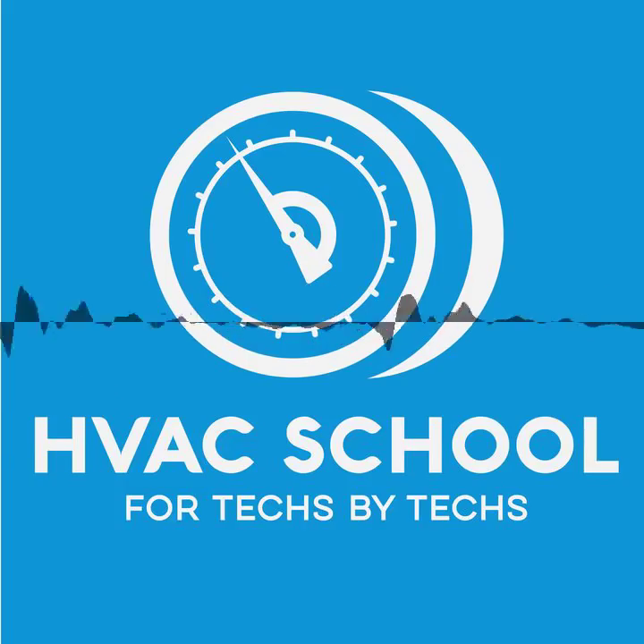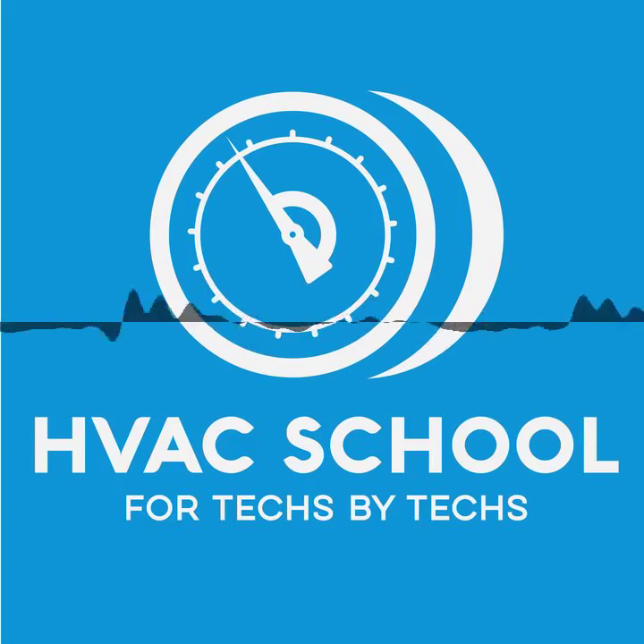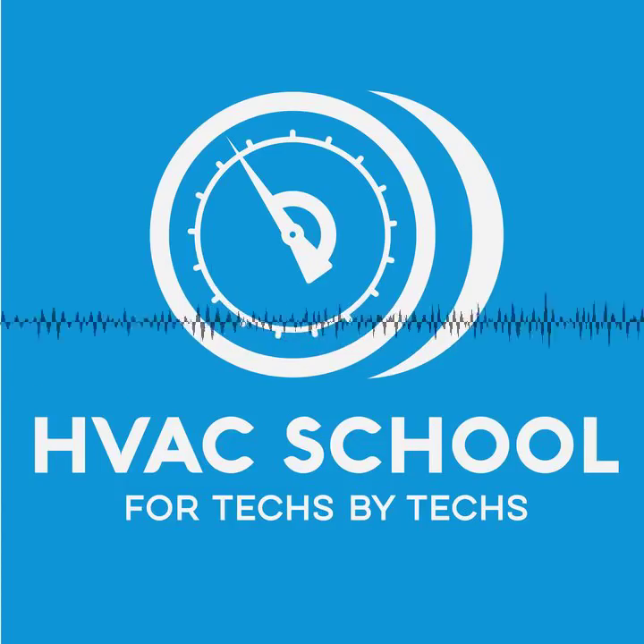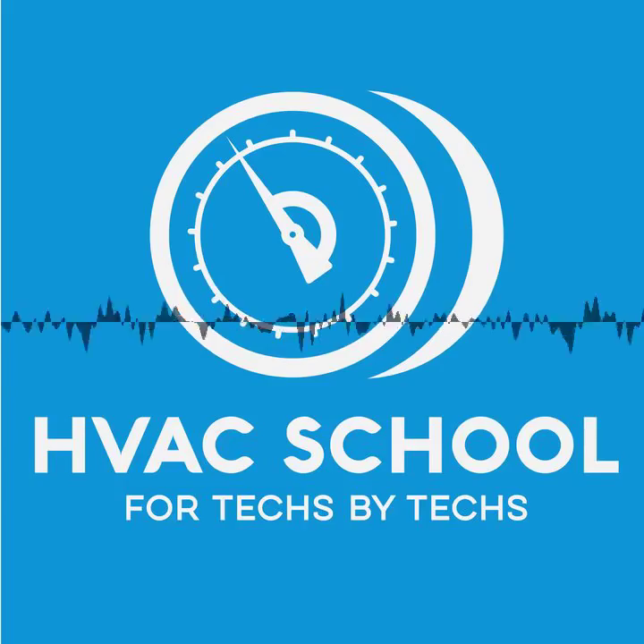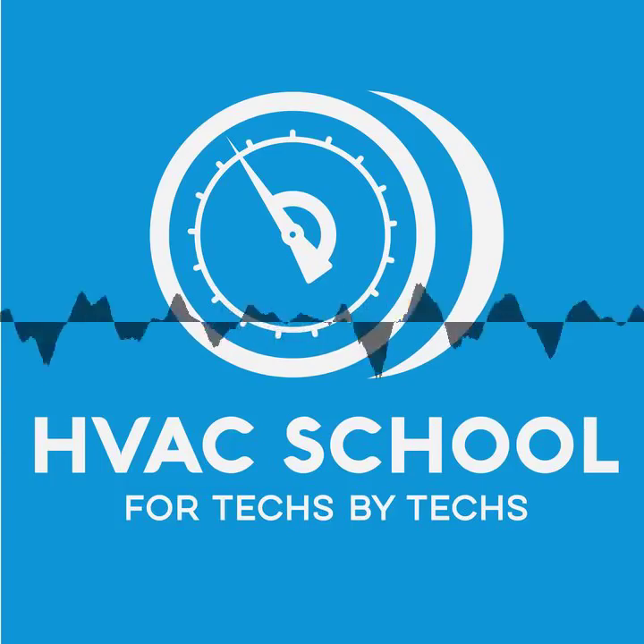You had also mentioned absolute pressure. When you say absolute pressure, how is that different than gauge pressure? With your standard gauges, if you have them open to the air, the gauge reads 0. Every pressure reading we take with those gauges, we're reading how much pressure we have above atmospheric pressure. But the truth is, at atmosphere, we really don't have 0. We have almost 15, somewhere around 14.7. Absolute pressure takes that into account. If you were to use a set of gauges calibrated to absolute pressure, when you unscrewed your hose before you even connected it to anything, you'd be reading about 15 pounds. And then when you read your refrigerant pressure, it would be about 15 pounds higher than what we typically see on our gauges today.